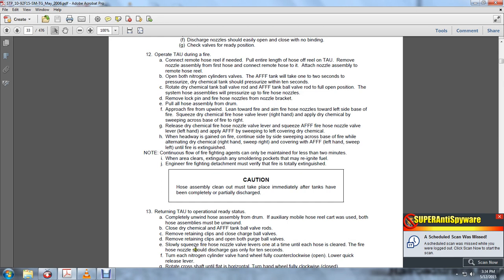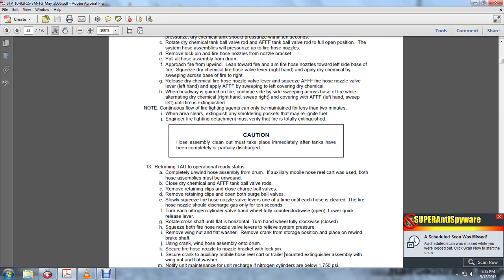The fire hose nozzle shall be discharged until gas flows for 10 seconds. Turn each nitrogen cylinder valve hand wheel fully counterclockwise to open. Lower the quick release lever. Rotate the cross shaft until the flat is horizontal. Turn the hand wheel fully clockwise and close.